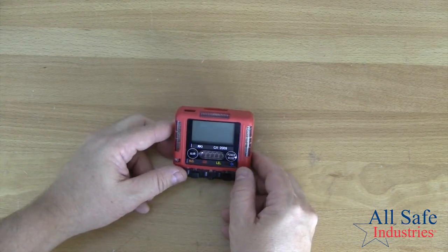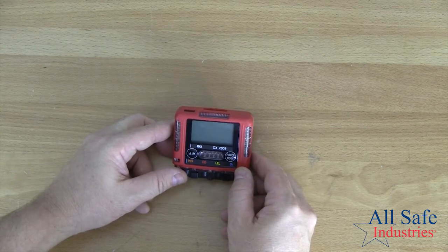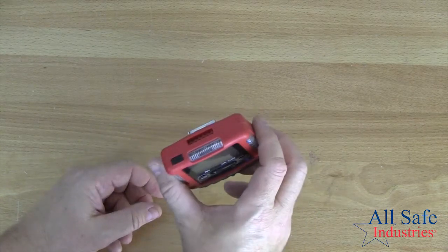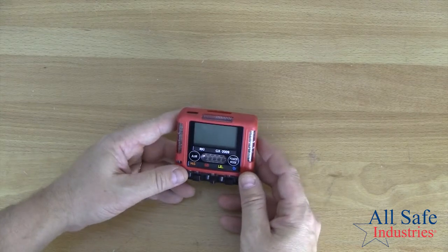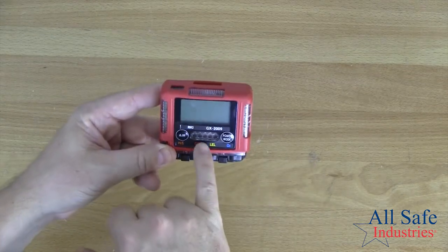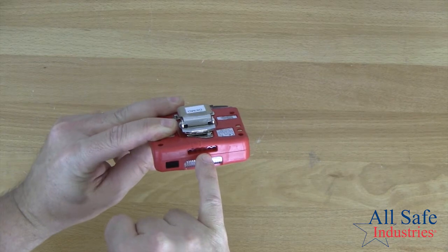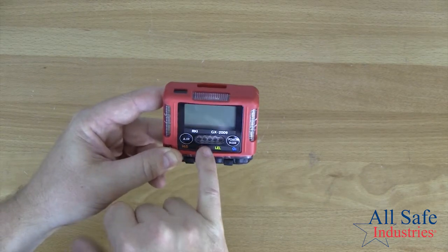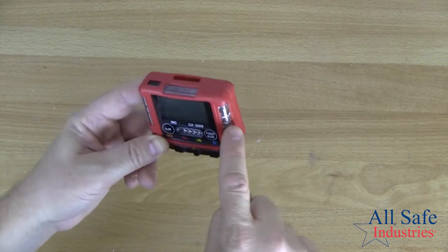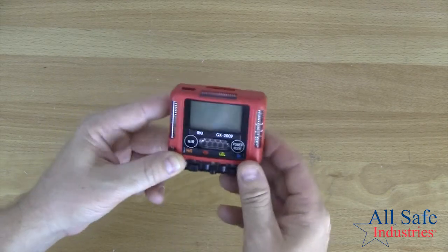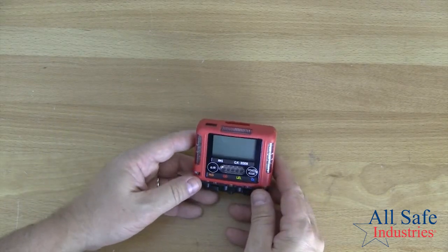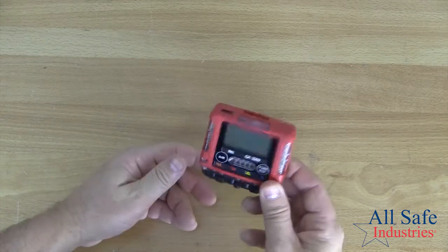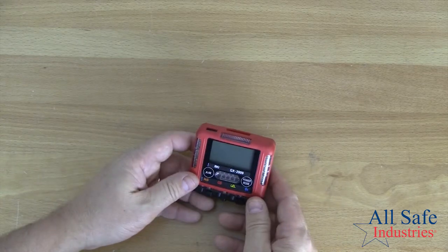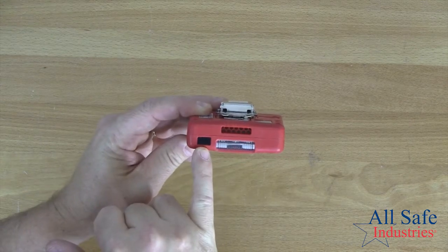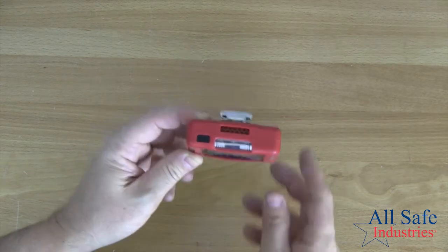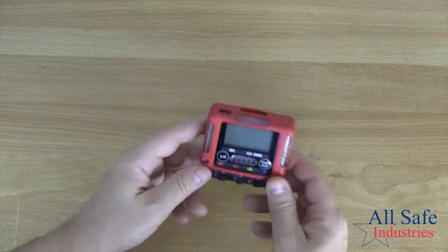It has a 3-way alarm: audible, visual, and vibration. So this unit will vibrate when it goes into alarm. You'll also have audible alarms, and the audible comes out of 2 different sound ports just to make sure that you can hear it from any angle. And then you have 3 bright red flashing LEDs on all 3 sides, so again you can see it from any angle. It's got large capacity data logging, so we can store up to 300 hours of information on this instrument, and then you would download that information through the infrared port. You need a separate infrared reader to pick up that information.